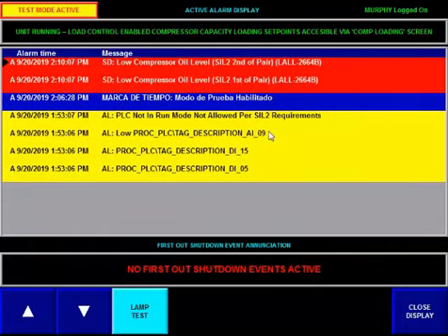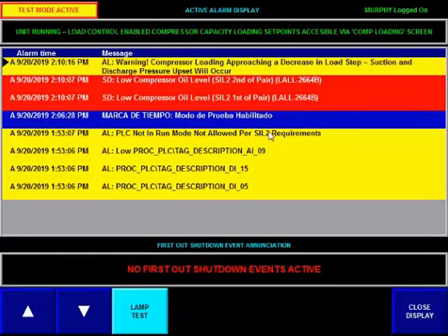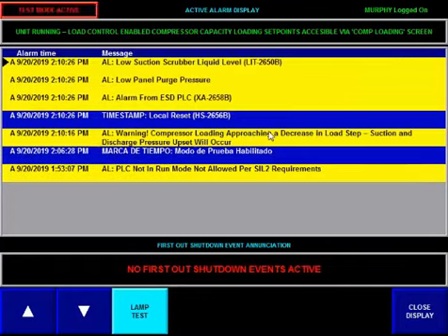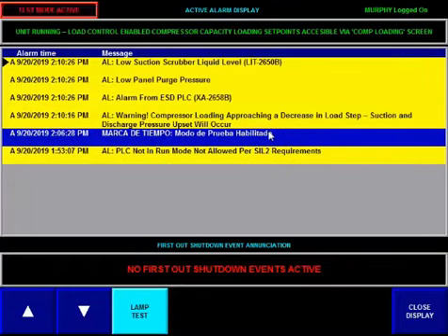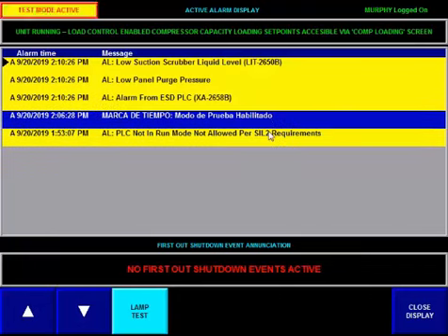You can see that the trip occurred, but you can see in the banner the unit's still running loaded. Now I'll hit the reset button to clear out the fault after I've restored the fuse. Unit's cleared out now. Now I'll go back to test mode, disable test mode, and the unit will continue running without any interruption.